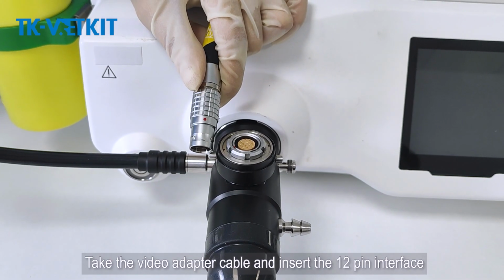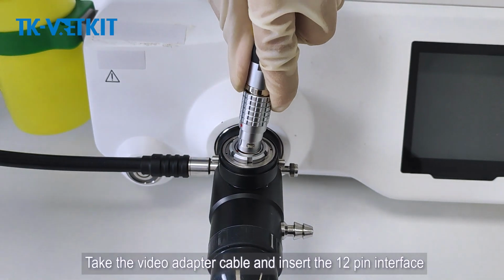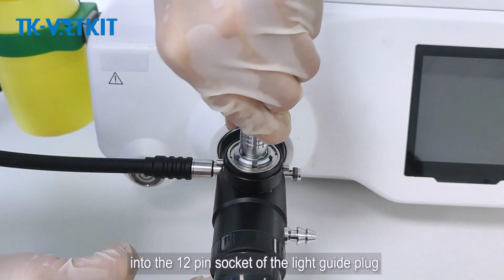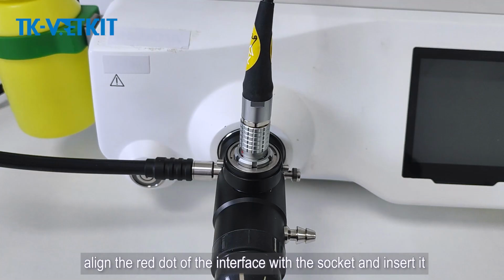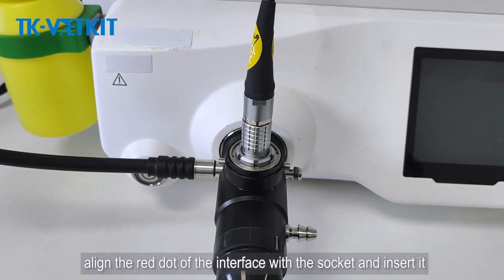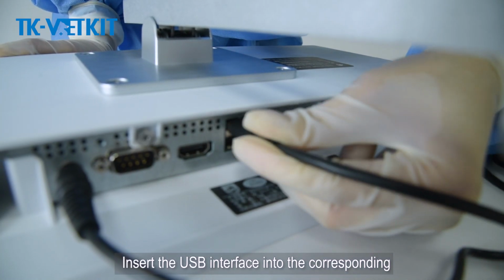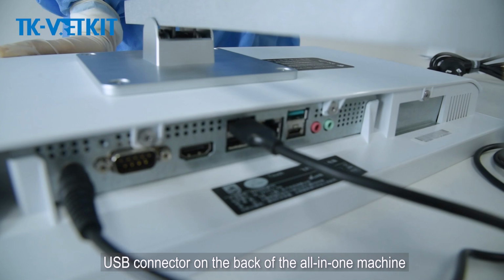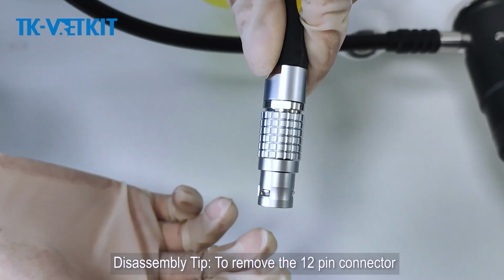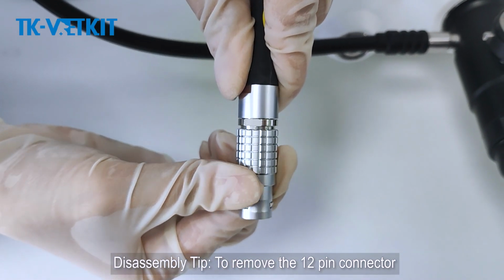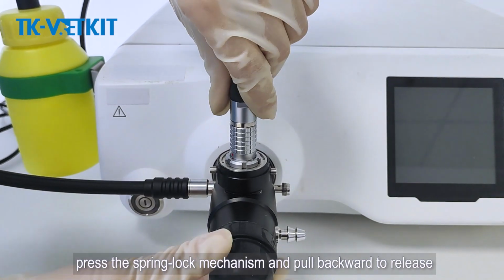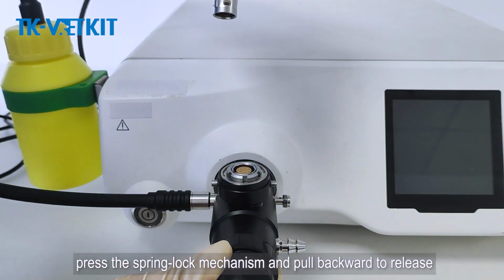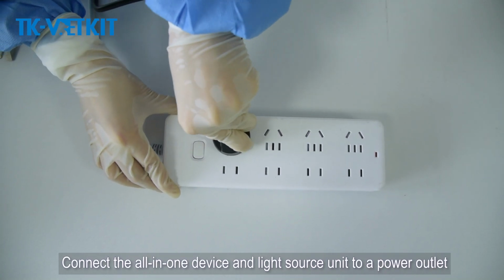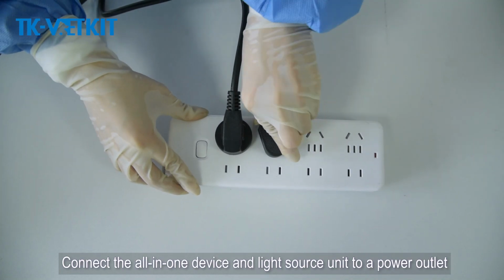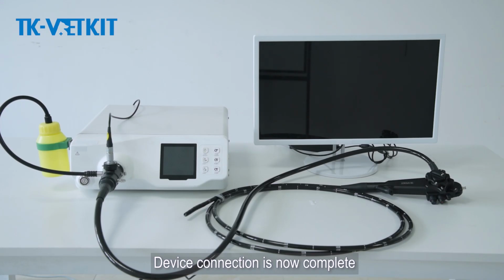Take the video adapter cable and insert the 12-pin interface into the 12-pin socket of the light guide plug. Align the red dot of the interface with the socket and insert it. Insert the USB interface into the corresponding USB connector on the back of the all-in-one machine. Disassembly tip: to remove the 12-pin connector, press the spring lock mechanism and pull backward to release. Connect the all-in-one device and light source unit to a power outlet. Device connection is now complete.